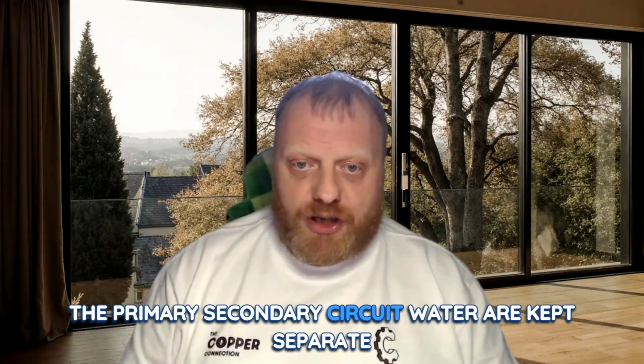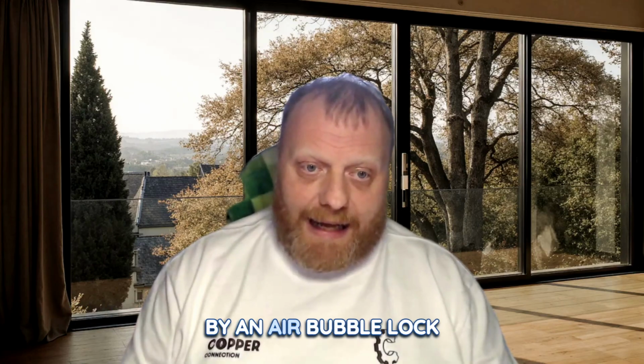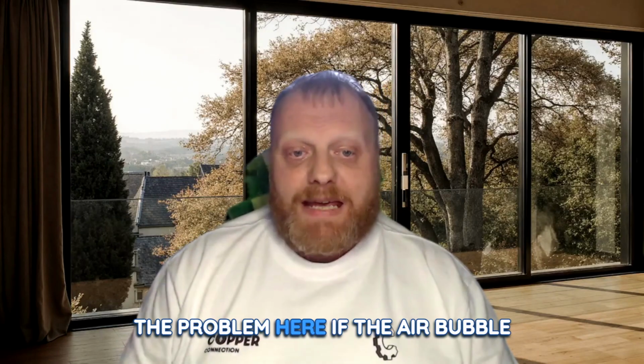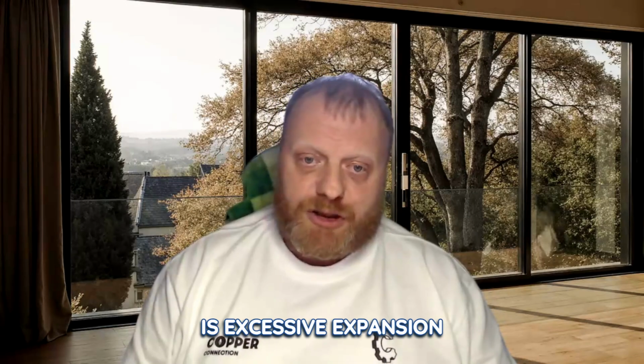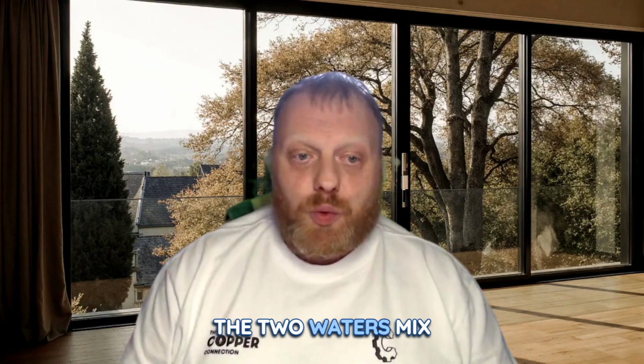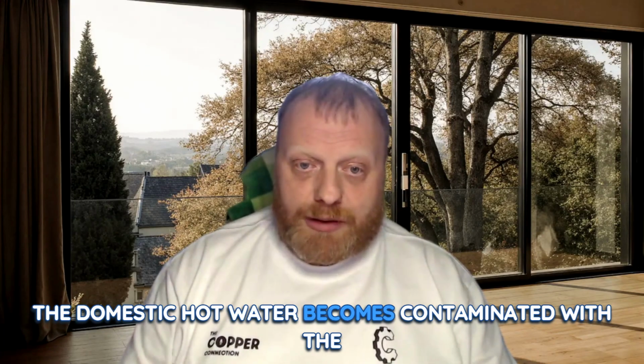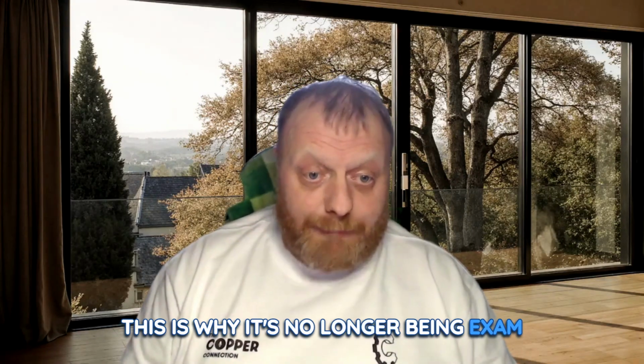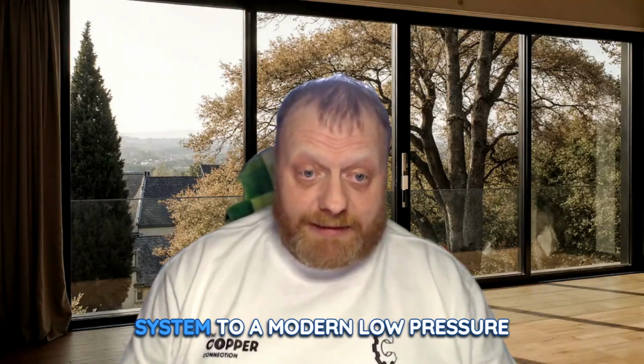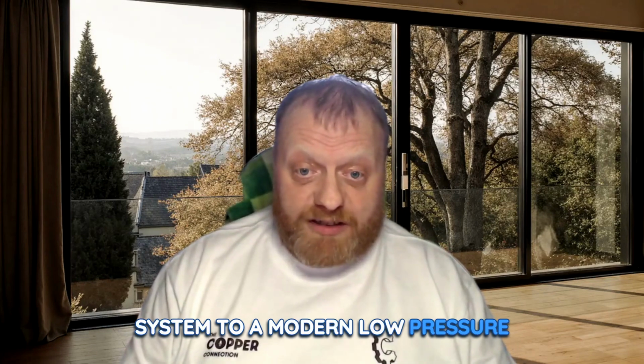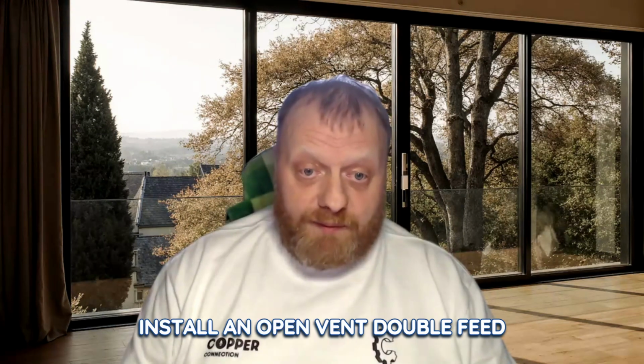The primary and secondary circuit water are kept separate by an air bubble lock inside a specifically designed cylinder. The problem here: if the air bubble is lost to excessive expansion, the two waters mix. The domestic hot water becomes contaminated with the boiler water. This is why it's no longer used. Exam tip: if asked to upgrade a primatic system to a modern low-pressure indirect system using the existing boiler, install an open vented double feed indirect cylinder.